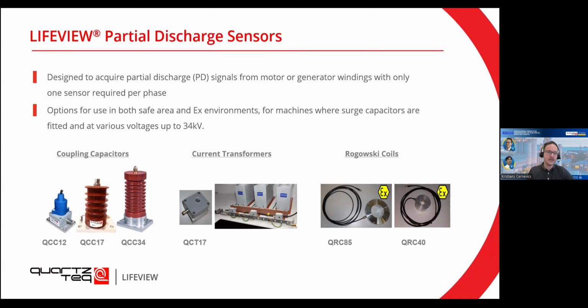On the other hand, if the machine already has an installation of surge capacitors, so the coupling capacitors would not work that well, then we suggest installing the current transformers. From the surge capacitor, you have your earth cable leading to the earth, and on this cable you can install the current transformer. The current transformer essentially works as an inductive sensor, so the more current goes through it, the higher the signal it will output to the analyzer.